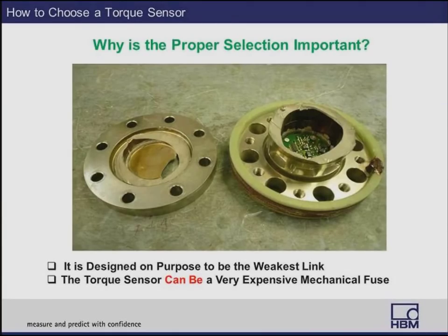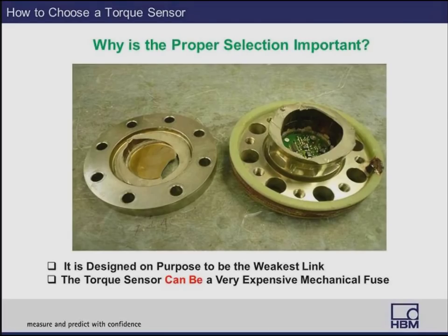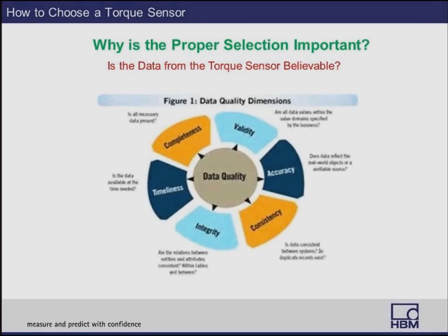Why is the proper selection of a rotating torque sensor important? It is designed on purpose to be the weakest link in the drivetrain. The reason for this is to direct torque to a specific area and place the strain gauges over that area — making the sensing area the weakest link. If something catastrophic happens mechanically, the torque sensor can act as a very expensive mechanical fuse, so proper selection is important to avoid mechanical failure. Also, it's important that the data from the torque sensor is believable and as least uncertain as possible, ensuring all electrical requirements are addressed so you can acquire the best possible torque data.